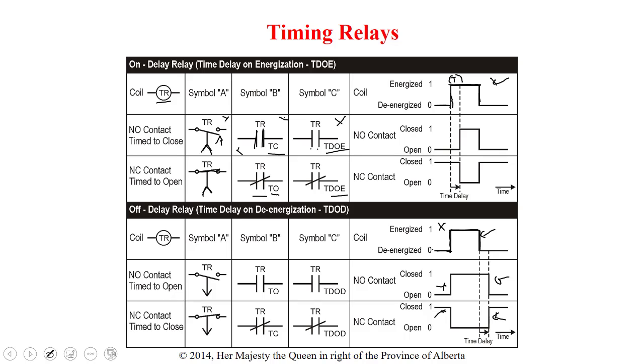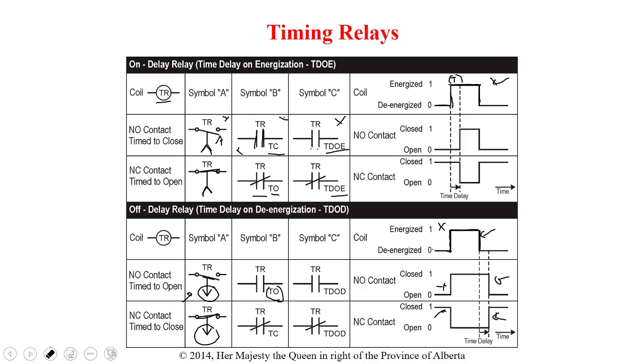So for the symbol, if we draw it like this, you notice that when it's on de-energization, the arrow points down. Okay, and once again, we can have open or closed. Another way to write that is a normally open contact, and it says time to open. So if this was a time contact, when I energize the coil, it would close. When the coil gets de-energized, it would stay closed for the elapsed time and then open back up. Another way to write that is TDOD.